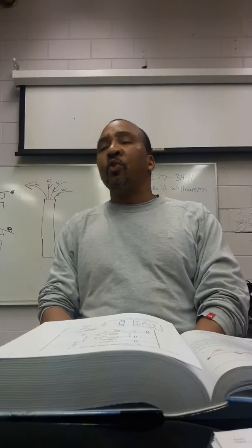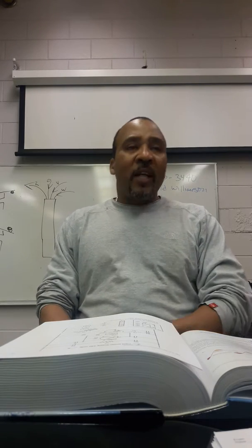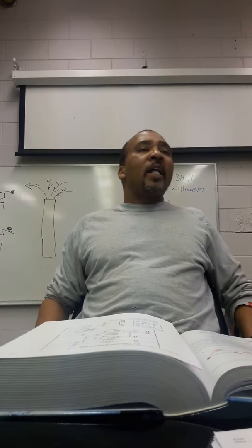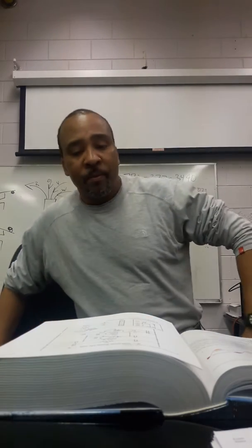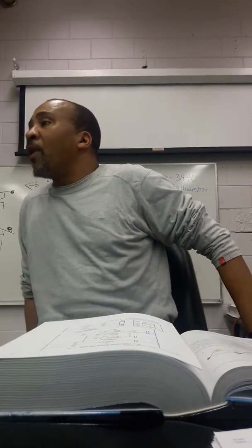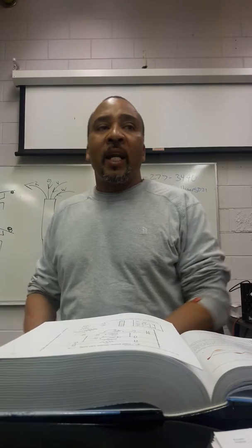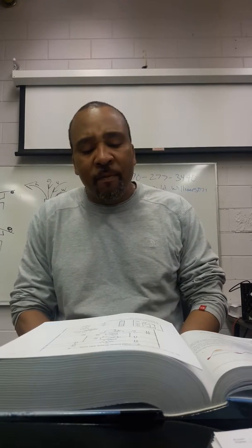I like starting off with the 24 volts. I want to know whether or not I got 24 volts. If I check this circuit and I got 24 volts, that lets me know a lot about our circuit. What's two things I know? The transformer is good. If the transformer is good and I'm getting 24 volts, it also lets me know what? I got line voltage. That is correct. If I got 24 volts, that means I have line voltage.